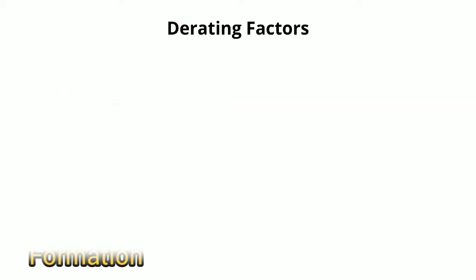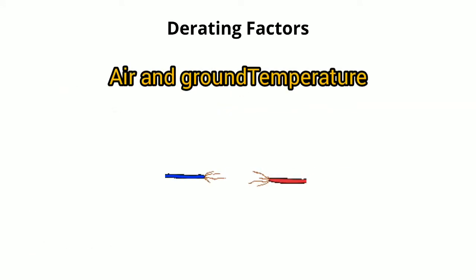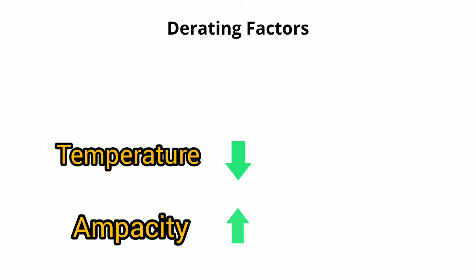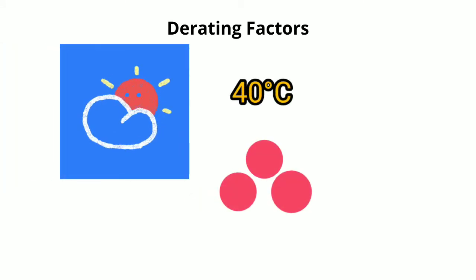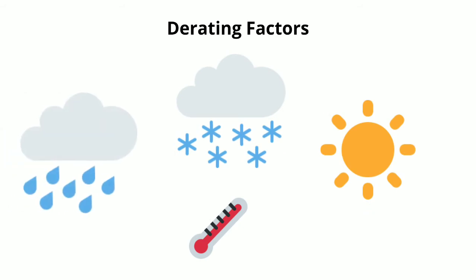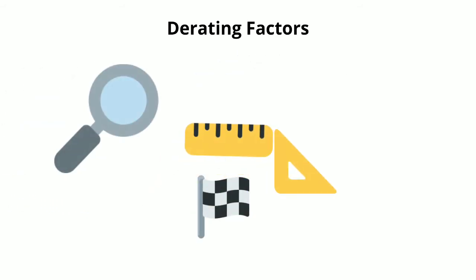Air and ground temperature. Cable temperature rise can be destructive. Cable current ampacity depends mainly on cable temperature. The lower the temperature, the higher the cable ampacity. Most cables' ampacity is rated at an ambient temperature of 40 degrees Celsius and a ground temperature of 35 degrees Celsius. If the temperatures are changed, then derating factor should be applied to the cable ampacity. This makes the cable work safer.